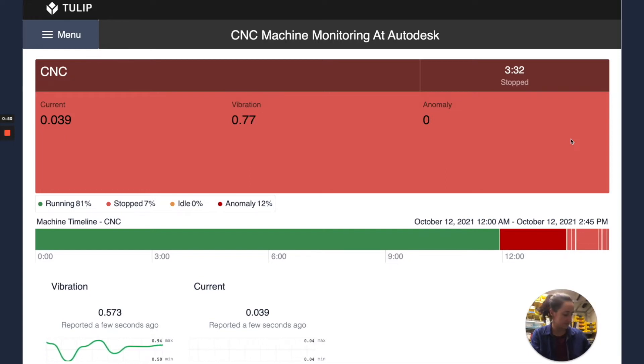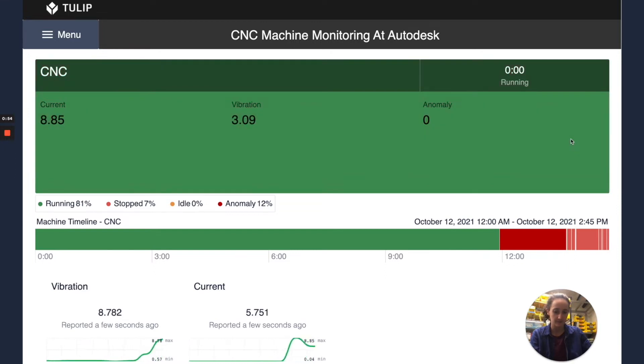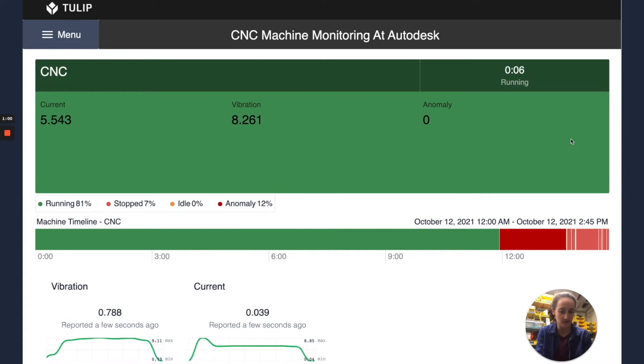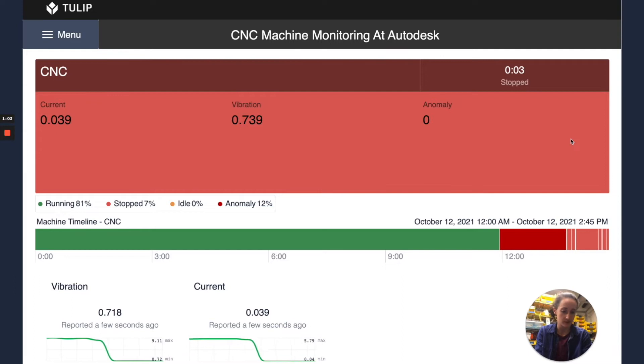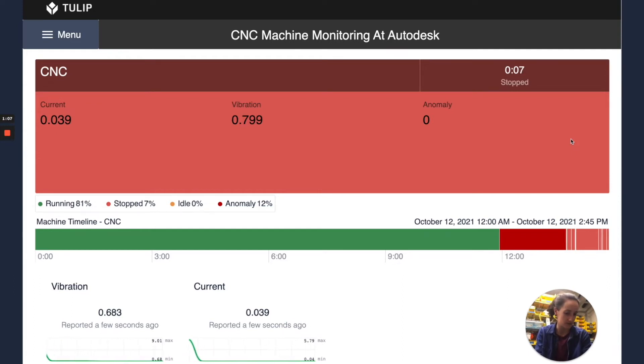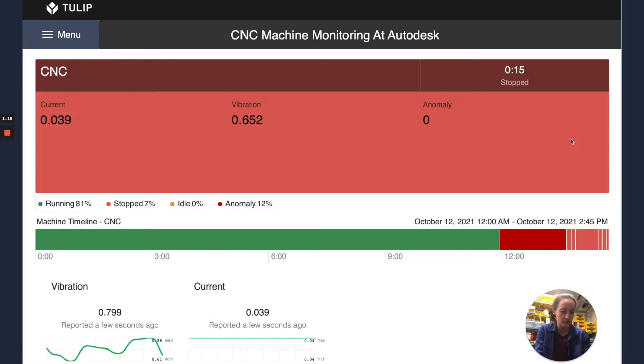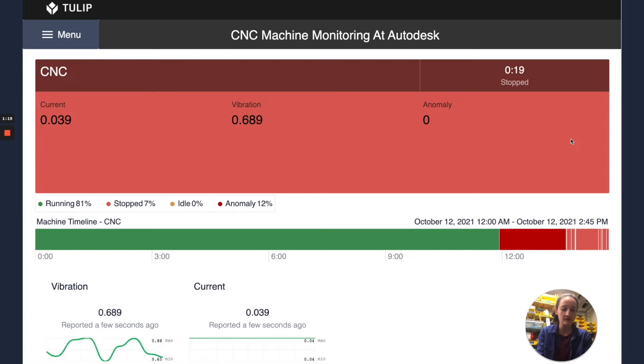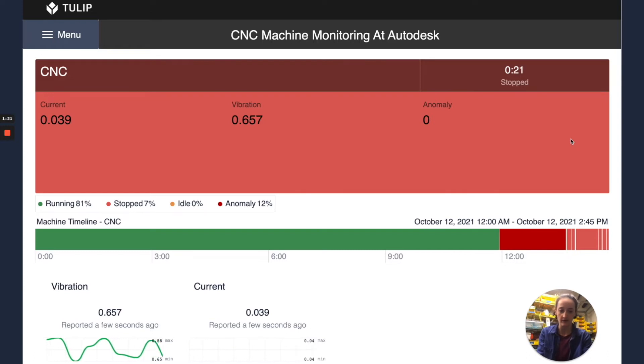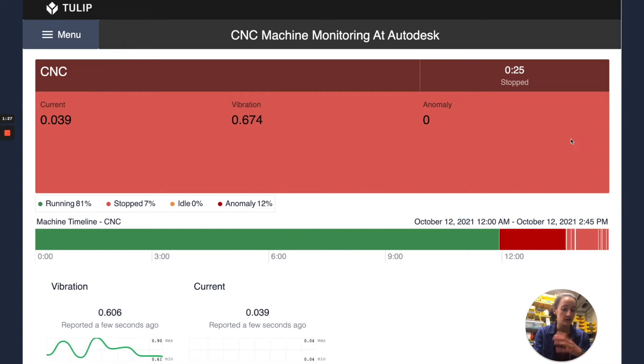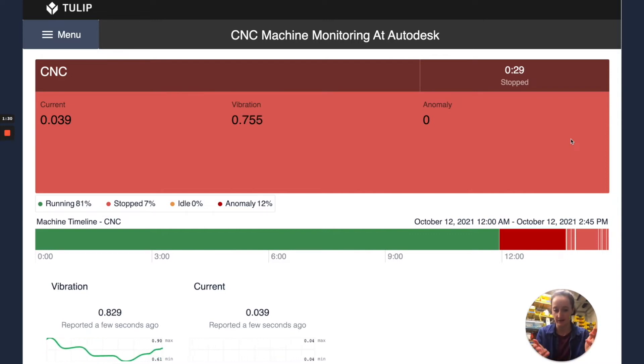I'm going to turn on the compressor and I'll turn it back off. And here we can see that just as expected the vibration sensor which is attached to the compressor reported higher vibration data when the compressor was on and the current which is monitoring the current going into the power of the compressor also went up when we turned it on. If you noticed the machine state also changed to running instead of stopped.